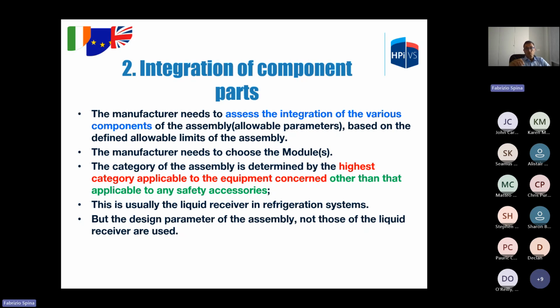The manufacturer needs to choose the modules. The modules are based on the category. The category of the assembly is determined by the highest category applicable to the equipment, other than that applicable to any safety accessory. So, if the highest category among the components is 3, then the entire assembly is classified as category 3. The category of safety accessories, which is category 4, is not taken into consideration.